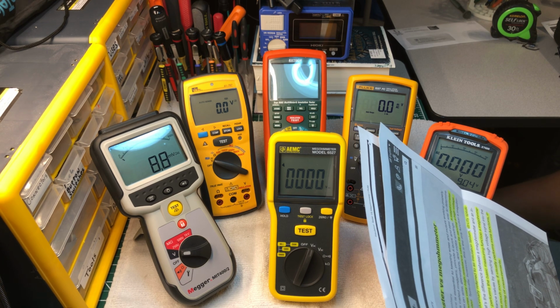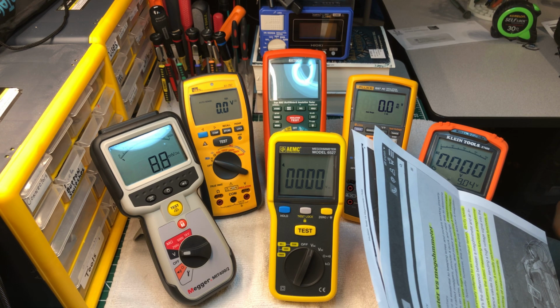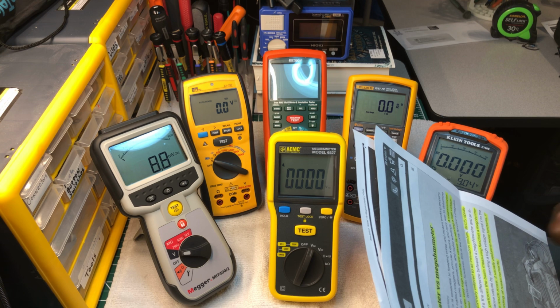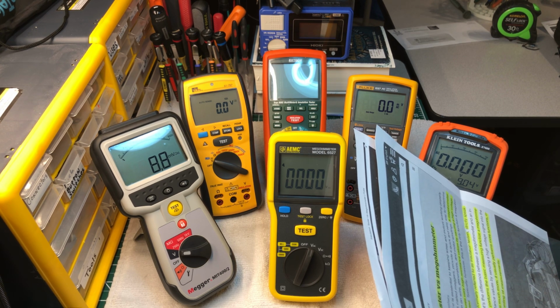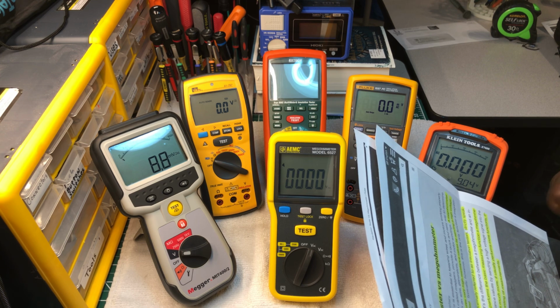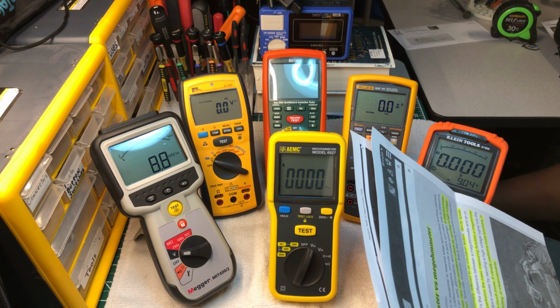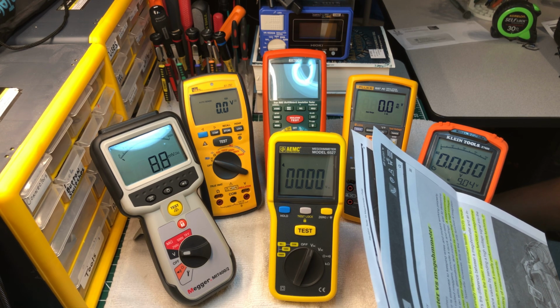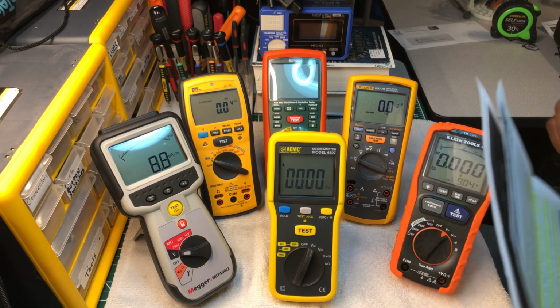Why? What's the difference between a megohmmeter and an insulation tester? An insulation tester performs the basic measuring function a megohmmeter does—measuring very high resistance values by sending a high voltage signal into the object being tested—and it often does much more. It usually performs more functions, including more complex testing and recording of measurements.